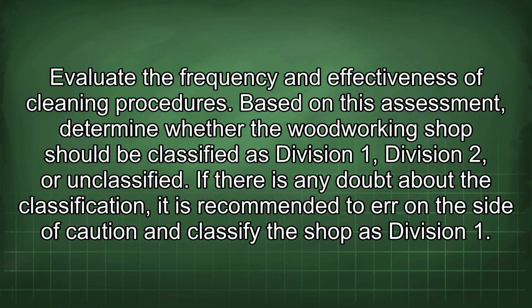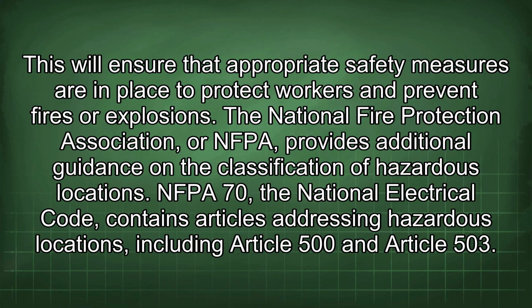If there is any doubt about the classification, it is recommended to err on the side of caution and classify the shop as Division 1. This will ensure that appropriate safety measures are in place to protect workers and prevent fires or explosions. The National Fire Protection Association, or NFPA, provides additional guidance on the classification of hazardous locations. NFPA 70, the National Electrical Code, contains articles addressing hazardous locations, including Article 500 and Article 503.